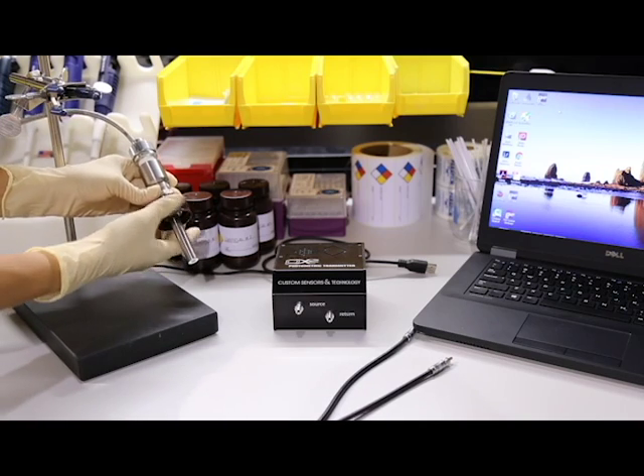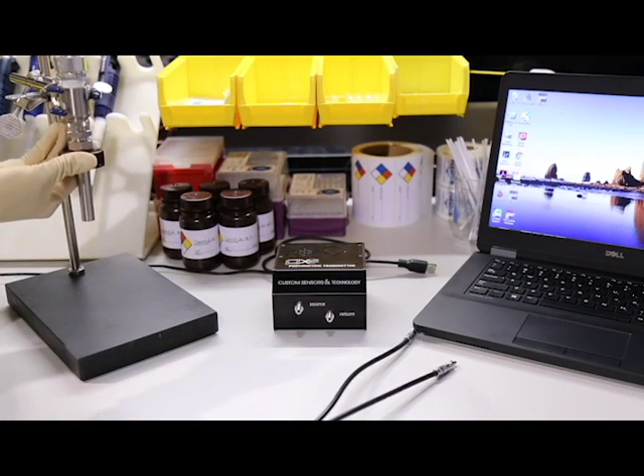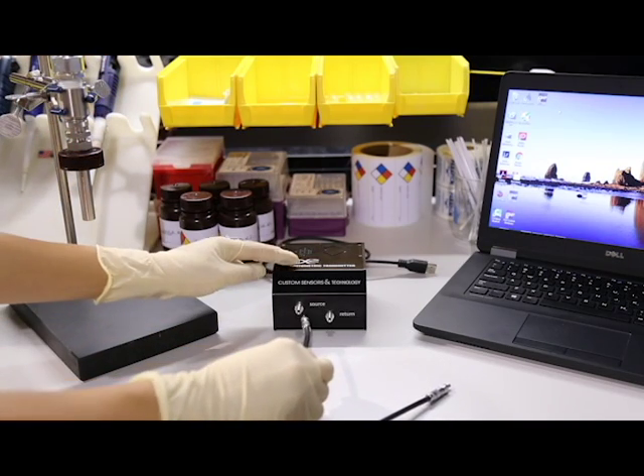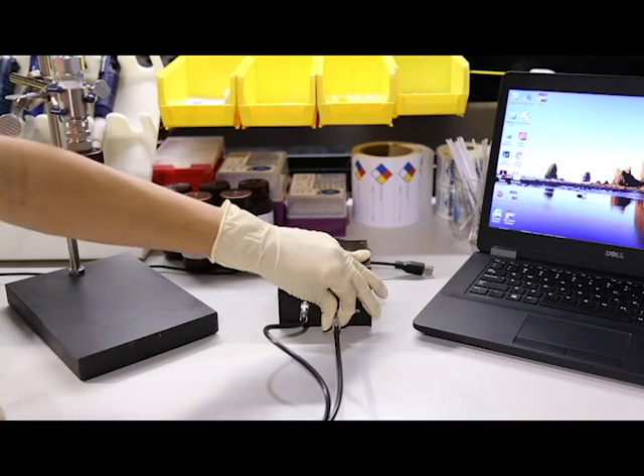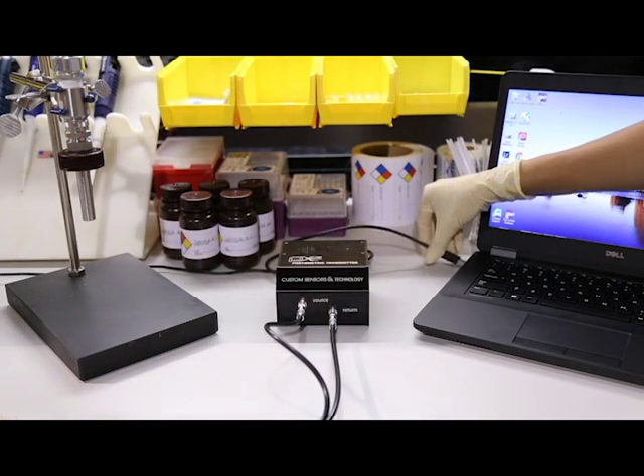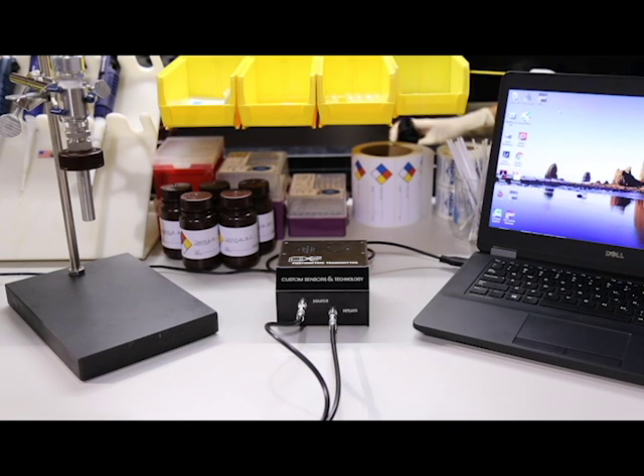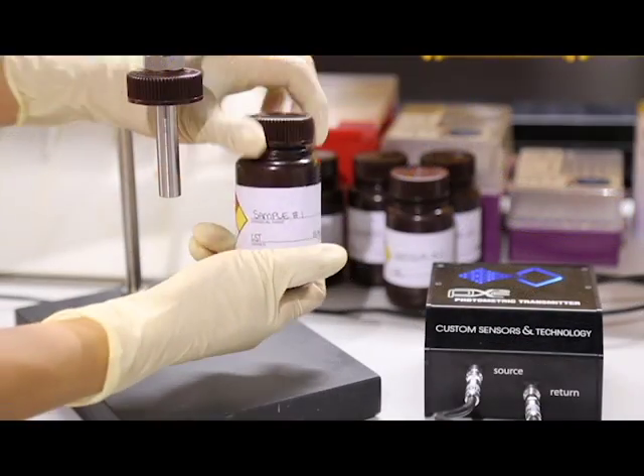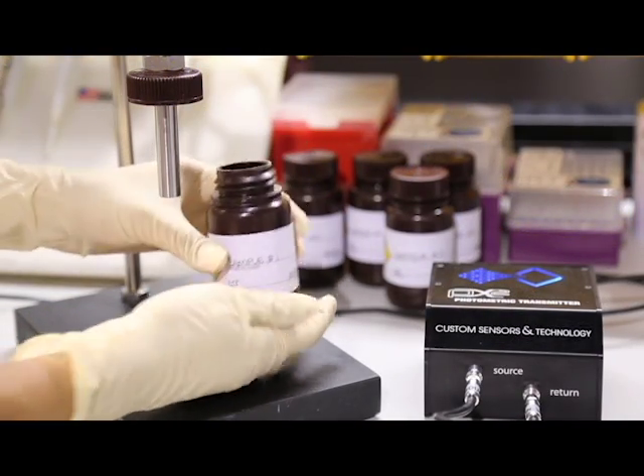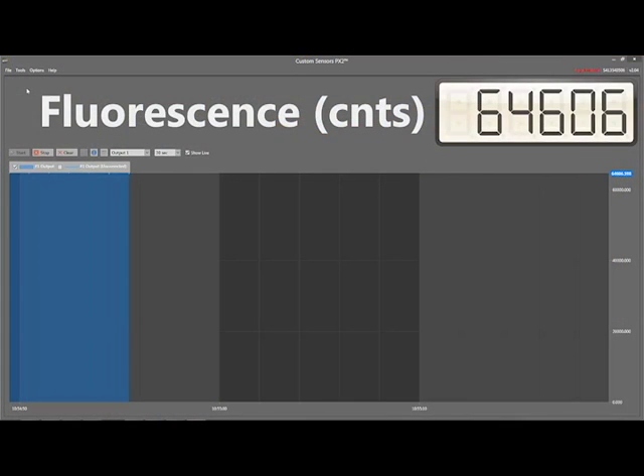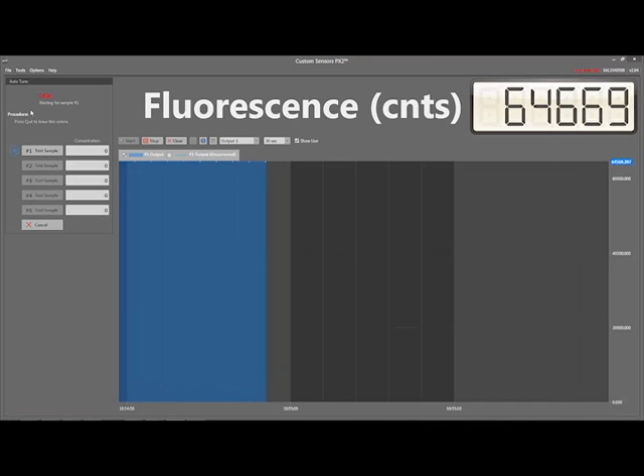First, I will begin by attaching my compression fitting to the probe and securing it to a ring stand. Then, I will connect my probe to the PX2, connect the PX2 to the computer, and power on the unit. Next, I will submerge the probe in the full-scale sample, open the PX2 control panel app, and allow the PX2 measurement to settle. Once the measurement signal has settled, go to the Tools drop-down in the menu bar and select Channel 1 Auto-Tune. The Auto-Tune panel will appear on the upper left side of the screen.